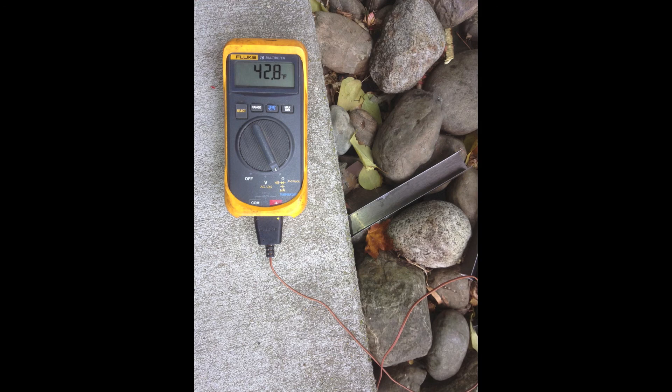The net stack temperature on the 92% furnace is 43 degrees, compared to 186 on the newer 80% and 327 on the old 80%. So perhaps now you can see why we use these new type of furnaces — we are not throwing away anywhere near as much of the heat as we used to. And that's my little comparison of the three efficiency furnaces.